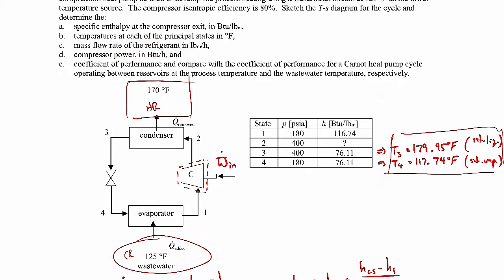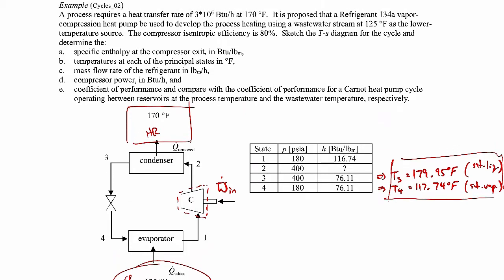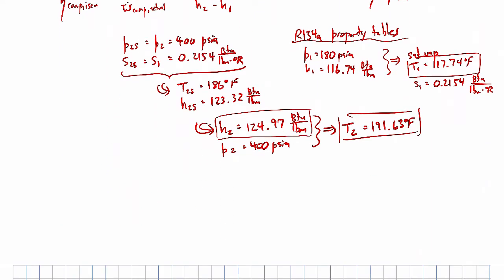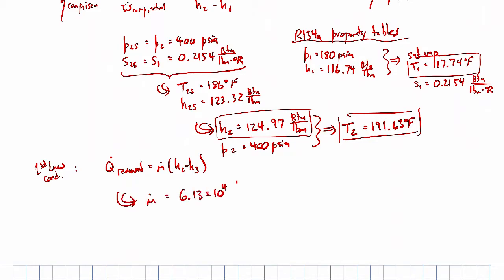Part C is finding the mass flow rate of the refrigerant in pounds mass per hour. We do a first law analysis on the condenser, drawing a control volume around it. We know the required heat transfer rate is 3 million BTUs per hour, and we know the specific enthalpies at the inlet and outlet. First law on the condenser gives: Q dot removed equals M dot times (H2 minus H3). Solving for mass flow rate gives 6.13 times 10 to the fourth pounds mass per hour.